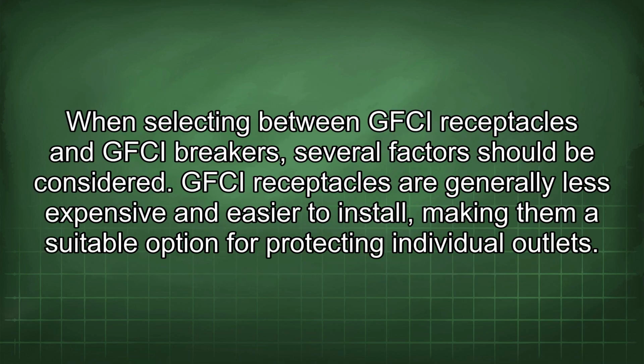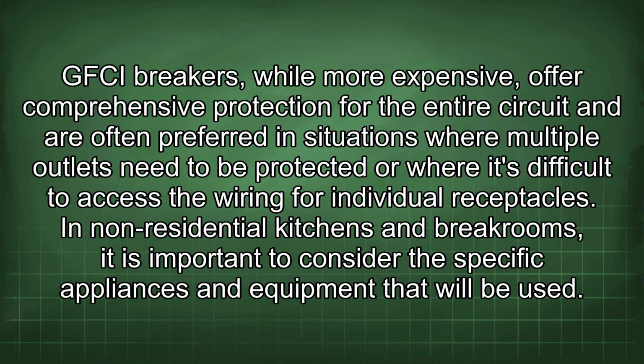When selecting between GFCI receptacles and GFCI breakers, several factors should be considered. GFCI receptacles are generally less expensive and easier to install, making them a suitable option for protecting individual outlets. GFCI breakers, while more expensive, offer comprehensive protection for the entire circuit and are often preferred in situations where multiple outlets need to be protected or where it's difficult to access the wiring for individual receptacles.